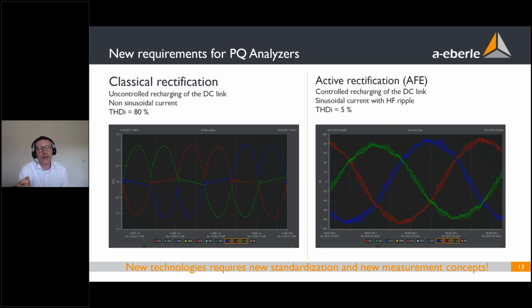The issue with a normal current transformer is that if I'm interested in measuring supraharmonics from an EV, for example, an inductive CT will not transfer these so-called supraharmonics to the secondary side. So even if our device is very accurate, we can only measure the accuracy that we actually receive from these components.